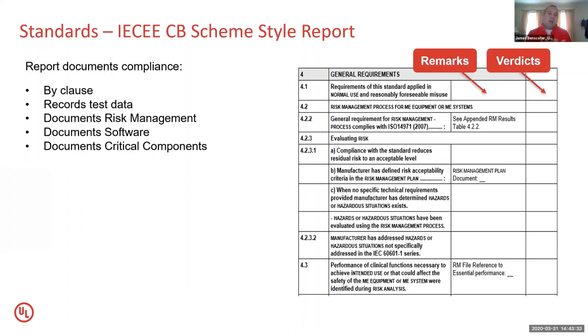This is an example of a typical IECEE CB scheme style report. These reports will typically document clause by clause how your device complies with relevant requirements, with remarks explaining why something may be not applicable. It may have information about where the evidence of compliance was found. So if I was doing clause 14, which is regards to software, I may be referencing a software architecture requirement. So I'll probably want to reference the software architecture document that was reviewed to show compliance. Same thing with critical components, which may be documented in there along with test data. So really when you get this one style of report, it gives you the ability to have all the relevant compliance information in one spot. So you're not trying to pull different documents from different spots. You have one concise list of information.